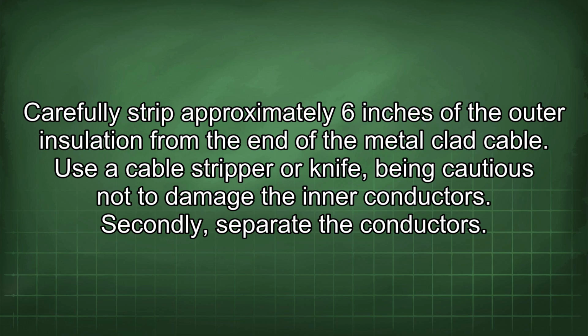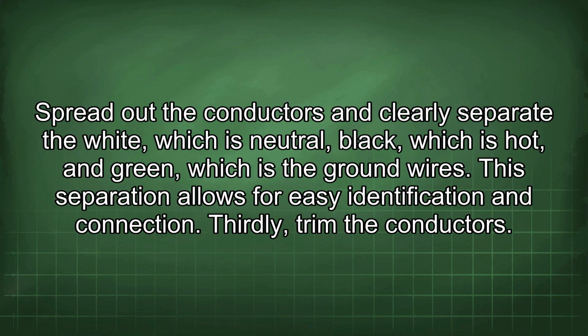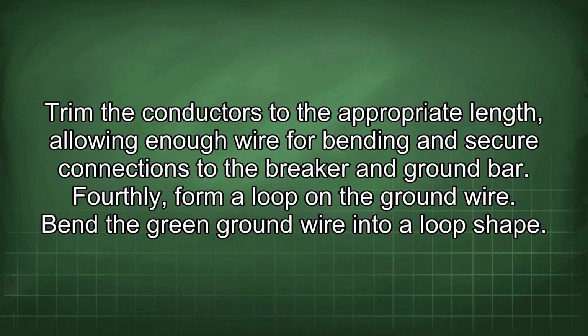Secondly, separate the conductors. Spread out the conductors and clearly separate the white, which is neutral, black, which is hot, and green, which is the ground wires. This separation allows for easy identification and connection. Thirdly, trim the conductors. Trim the conductors to the appropriate length, allowing enough wire for bending and secure connections to the breaker and ground bar.